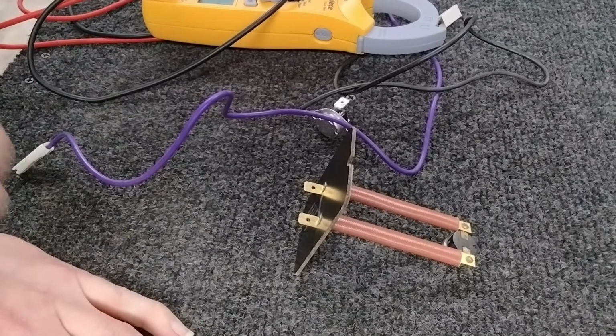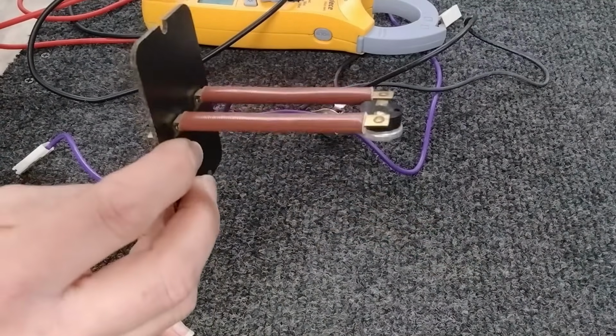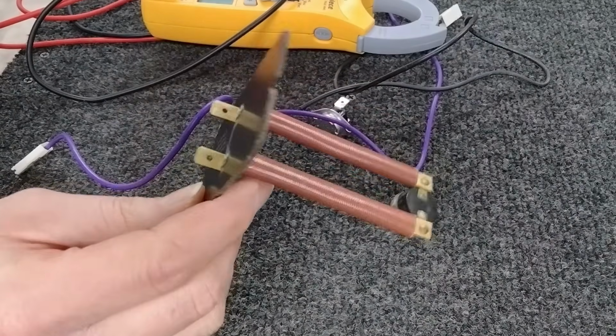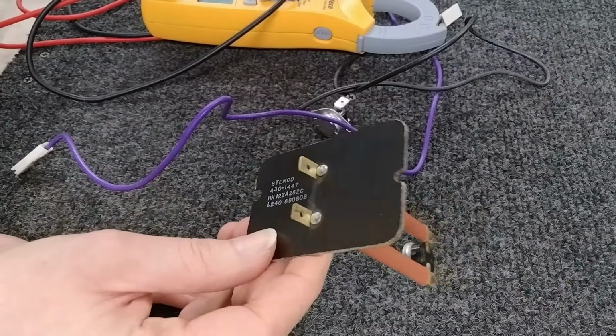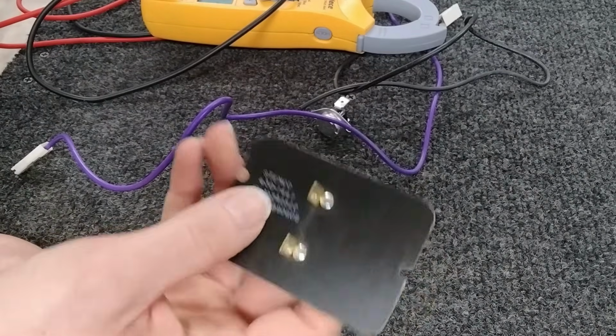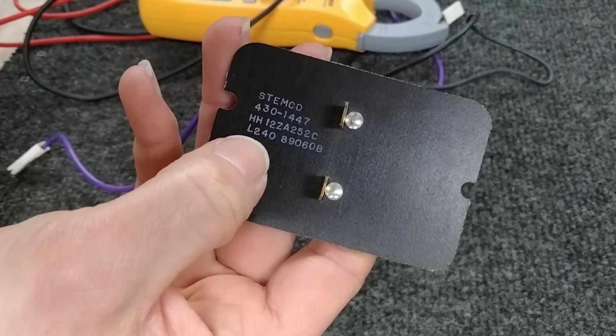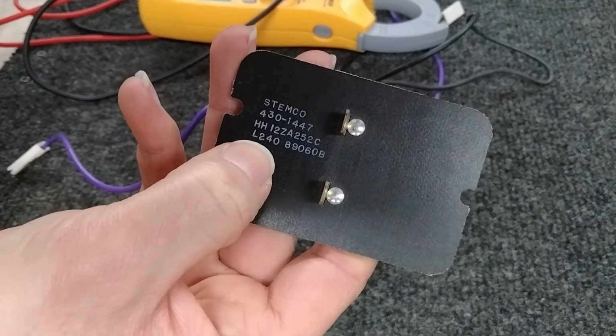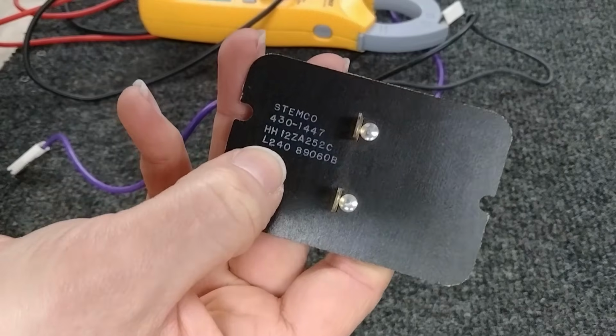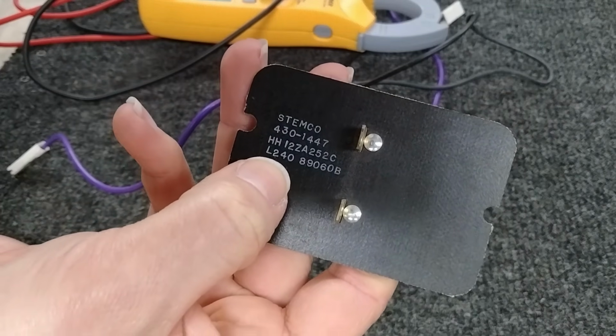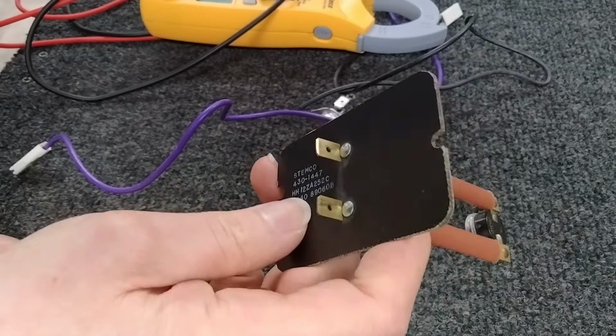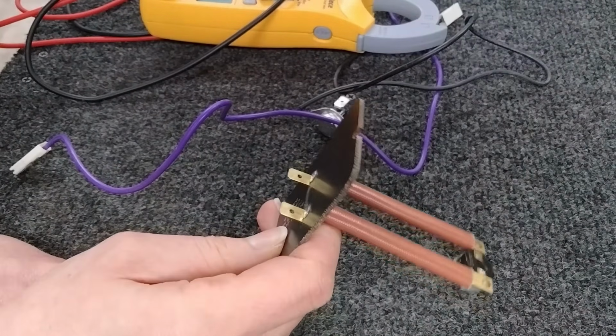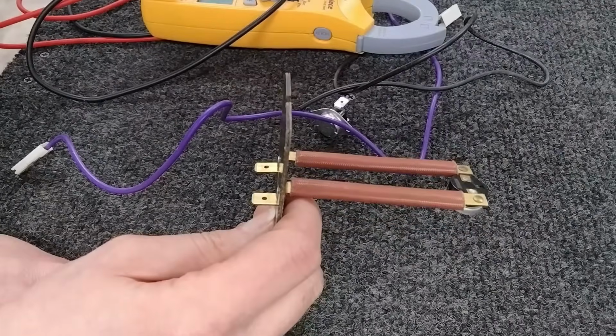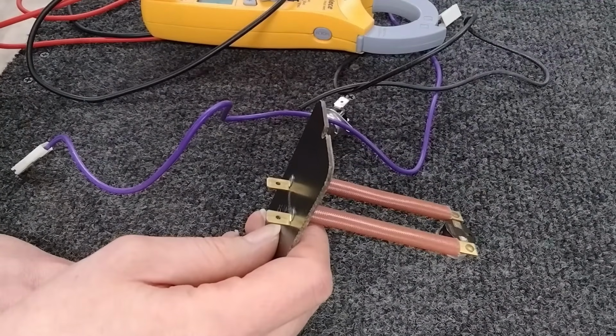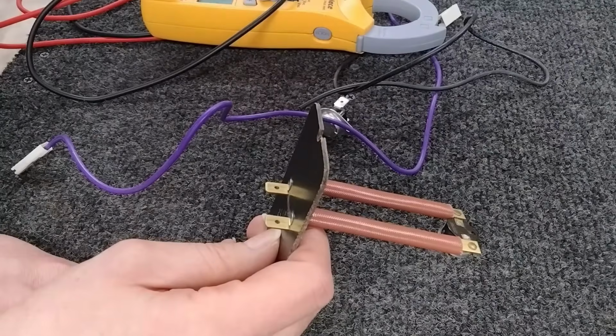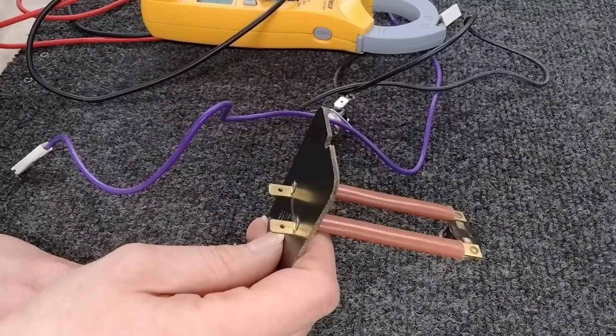engineers. So say you are getting a code for open high limit switch. You jump around it, everything seems to be working, boom, you're like, all right, it's this part. And again, you're gonna look for that temperature on there. This is a pretty high temperature high limit switch. It's 240. Most of them are kind of lower, around the 130 to 180 range. But if you do jump around that, it seems to work, everyone's happy, you buy a new one, you put it in there, and then a few hours later to a day or two later, it does it again. Boom, high limit switch open.